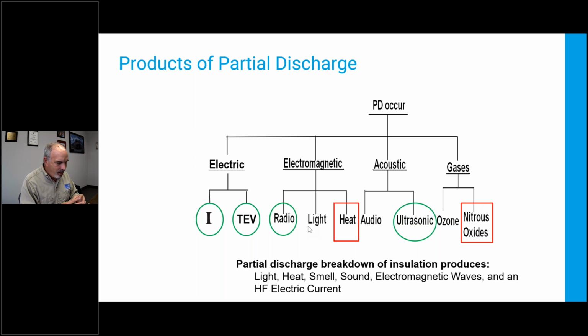Now, what also happens is that you get sound waves in the ultrasonic band, which is a lot higher than the range of human hearing. It's 40 kilohertz sort of territory. That is much more common. There's a lot more energy in that band from surface discharge, and so we can use that to detect PD. That's why it's got a green circle around it.